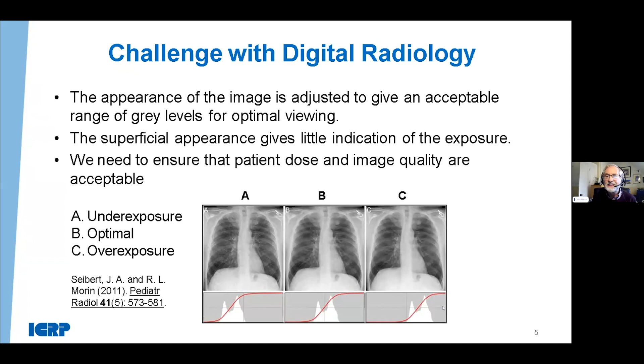There are challenges with digital radiology because the appearance of the image is adjusted to give an acceptable range of grey levels for optimal viewing. So the superficial appearance gives little indication of the exposure, but we need to ensure that patient dose and image quality are acceptable. If you see these images of chest x-rays, the one on the left is underexposed, the one on the right overexposed, but for a superficial view, you don't see that. It's only when you look at the details. So we've got to overcome these difficulties.